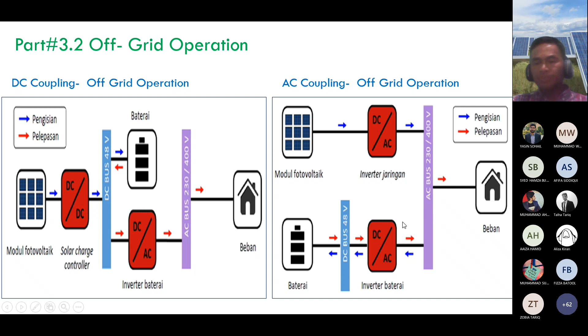But for the AC coupling, as we can see here, the photovoltaic module goes directly to the inverter. So we have two inverters here: one inverter for the PV module and one inverter for the battery. This one inverter is two-way, so it will charge the battery coming from the AC bus, and also deliver power from the battery to the AC bus, or to the load.